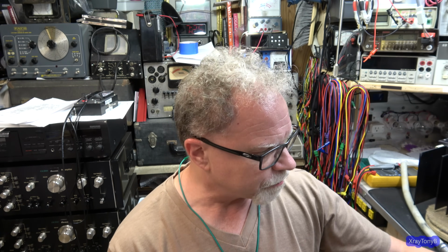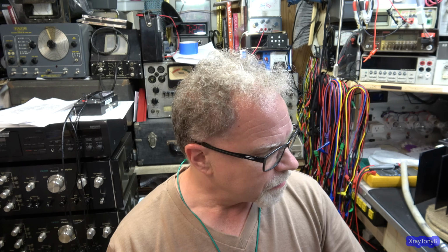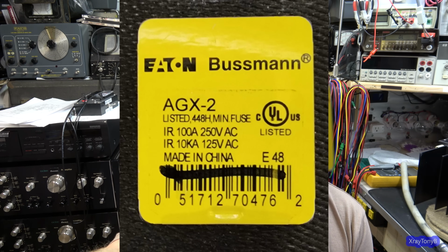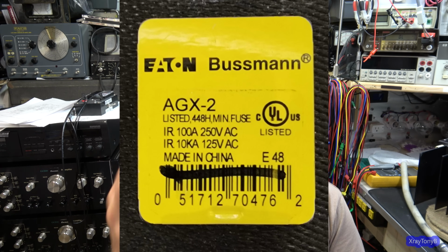So anyway, long story short, make sure that the maximum voltage rating of the fuse exceeds the voltage the circuit will have across it in the open circuit when that fuse blows open. Okay, so in other words, if you're protecting a mains voltage circuit, make sure you have a 250 volt fuse, not a 32 volt fuse. Now, what are these numbers here? These say IR, 100 amp, and what's it say, 10,000 or 10 kiloamps.